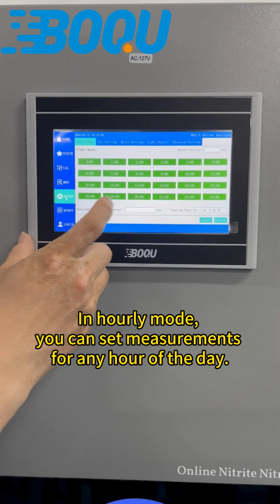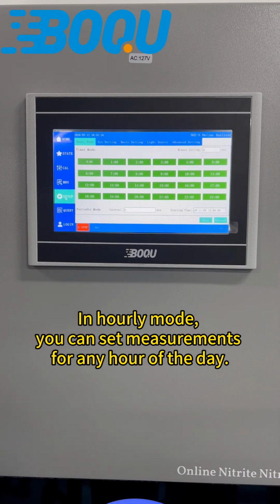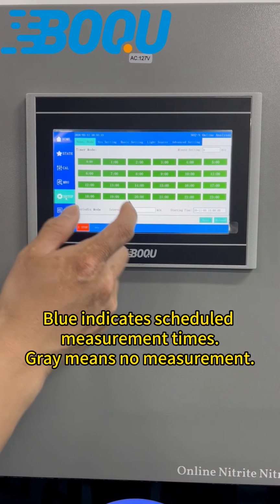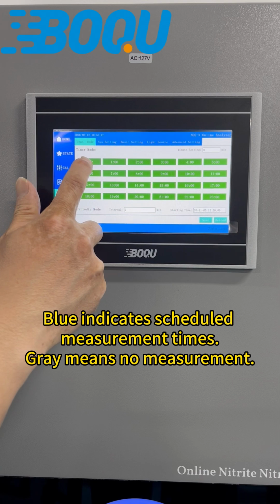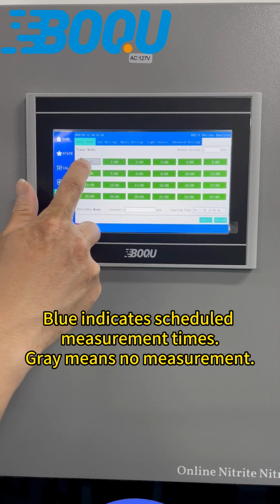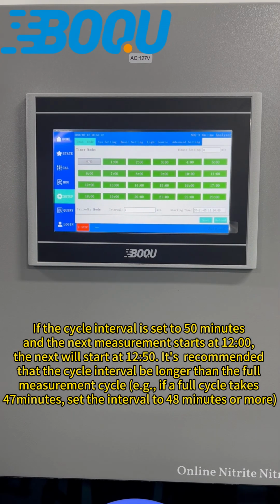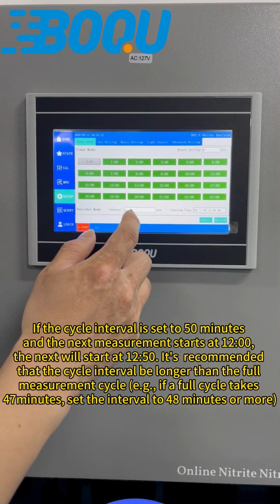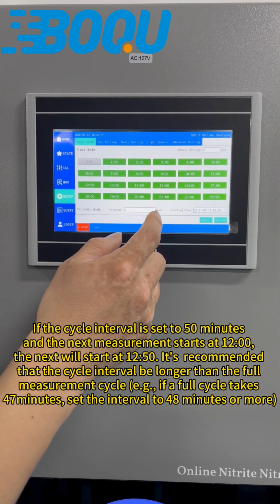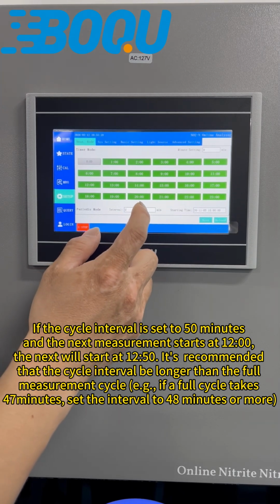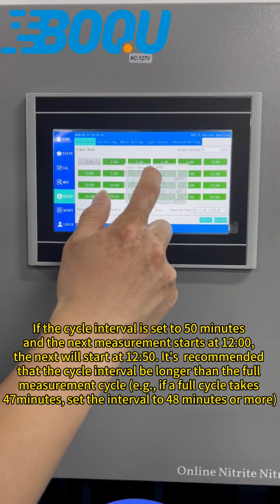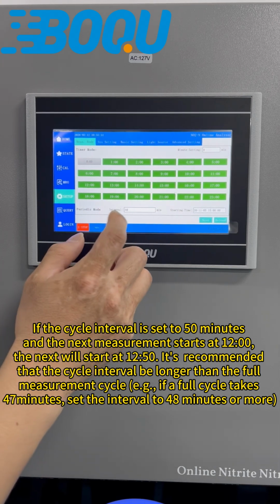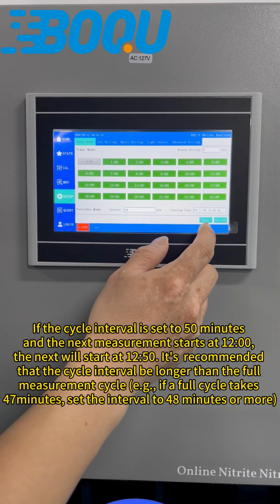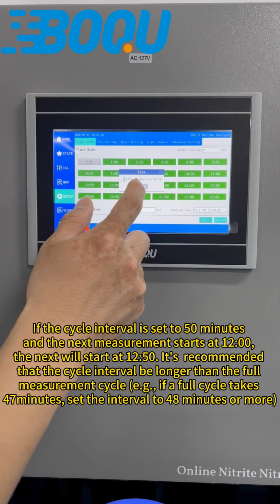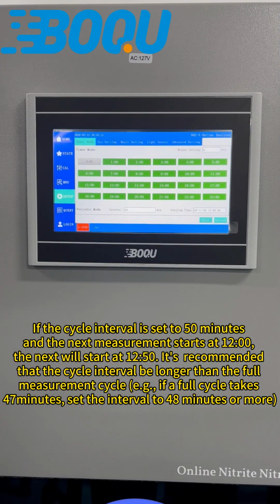In hourly mode, you can set measurements for any hour of the day. Blue indicates scheduled measurement times, but gray means no measurement. If the cycle interval is set to 50 minutes and the next measurement starts at 12 o'clock, the next will start at 12:50. It's recommended that the cycle interval be longer than the full measurement cycle, so if a full cycle takes 47 minutes, set the interval to 48 minutes or more.